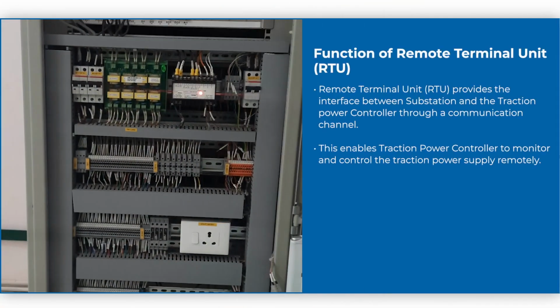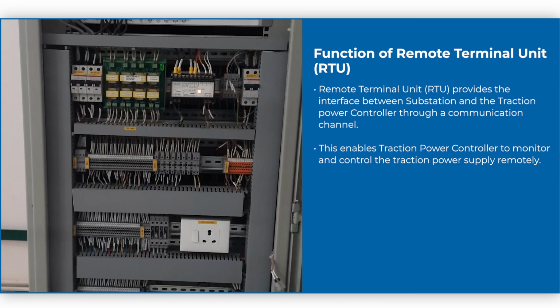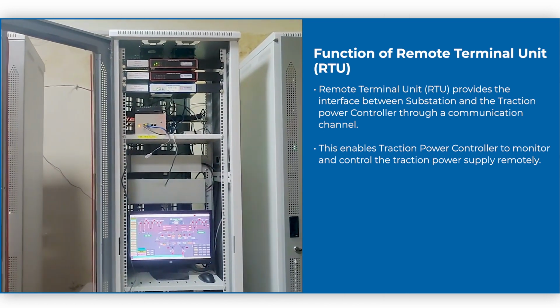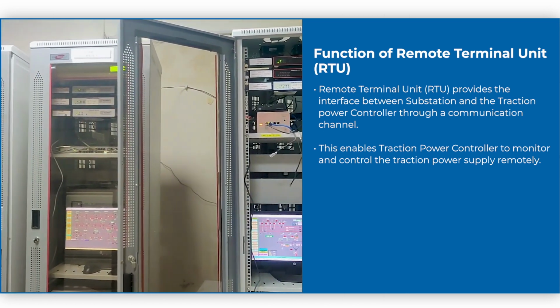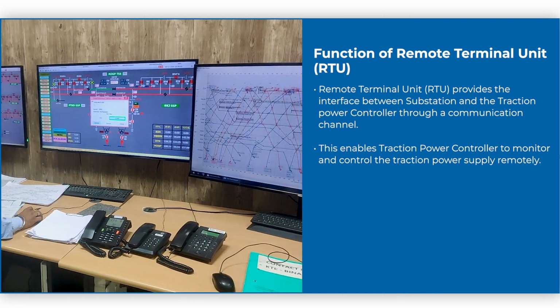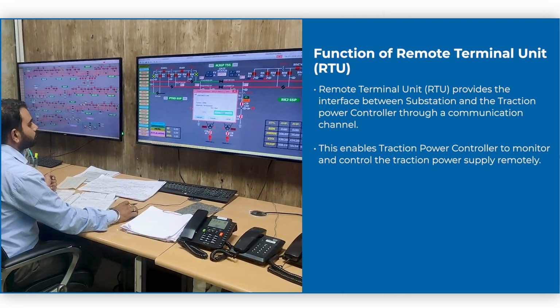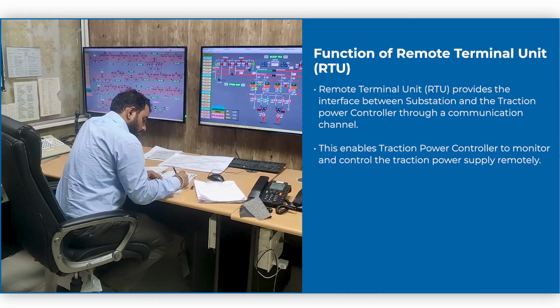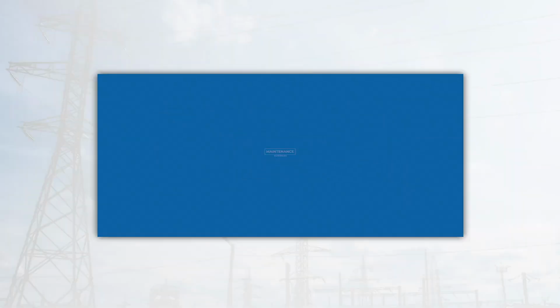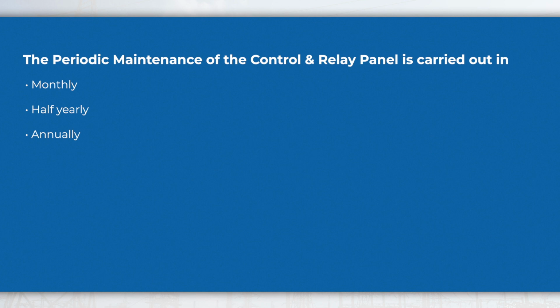Remote Terminal Unit RTU provides the interface between substation and the traction power controller through a communication channel. This enables traction power controller to monitor and control the traction power supply remotely. Maintenance schedules. The periodic maintenance of the control and relay panel is carried out in monthly, half-yearly, annually.